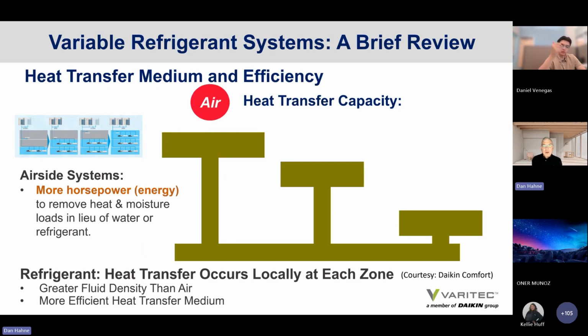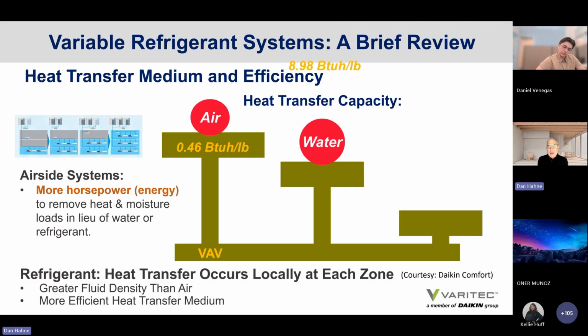To give you an example, air can carry only 0.46 BTUs per pound of air. So you need a lot of air to move the BTUs necessary to condition a building. If you look at chilled water, which is a more dense heat transfer medium, water carries 8.98 BTUs per pound of water. And because water is more dense, it carries a lot more energy with a lot less volume. This is why chilled beam systems and decoupled hydronic systems have become popular high-performance design strategies, because it takes a lot less pumping horsepower to move the sensible energy from a building than it would otherwise require for air.